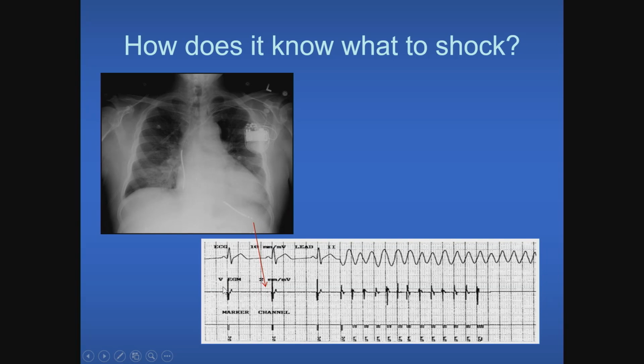So if the signal goes above the sensitivity bar, the device on the marker channel tells us that it thinks it sees a heartbeat. So it says VS here to tell us that it's seen a heartbeat. Here's another marker that shows that it saw a heartbeat. And you can see here when the fibrillation starts that the marker goes much faster. And we basically tell the device that if you see too many of these sensed events within too short a period of time, you should charge up and shock the patient.